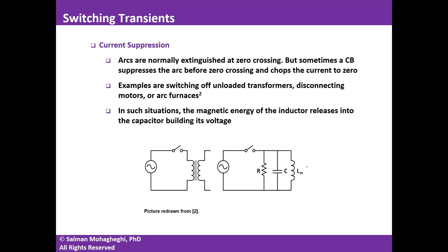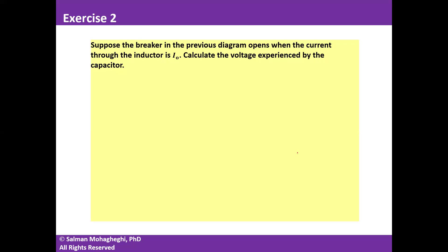Current suppression occurs in many situations: transformers under no-load conditions being disconnected, motors being disconnected, and operation of arc furnaces. During this time, some interesting transients occur. Consider an unloaded transformer being disconnected with non-zero current, meaning some magnetic energy is stored in the inductor, which will then discharge into the capacitor when the circuit breaker is opened. Please pause the video to calculate the maximum voltage experienced by the capacitor.